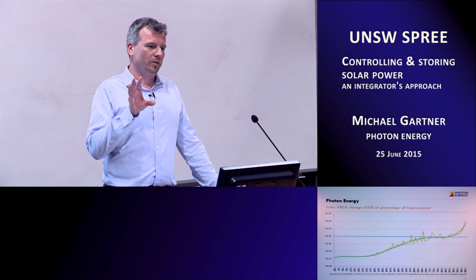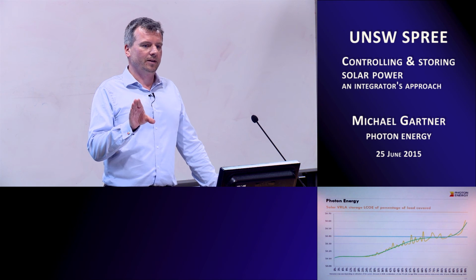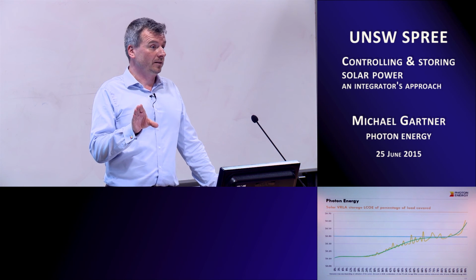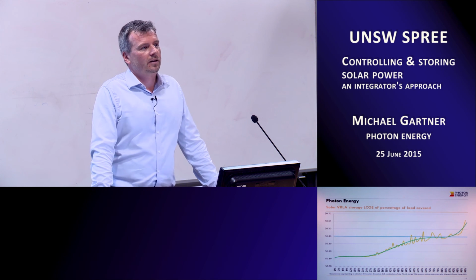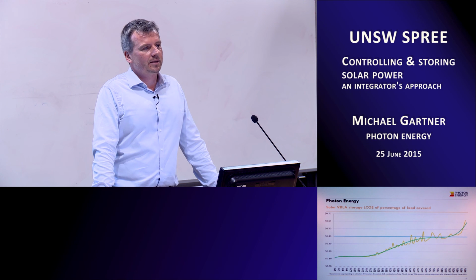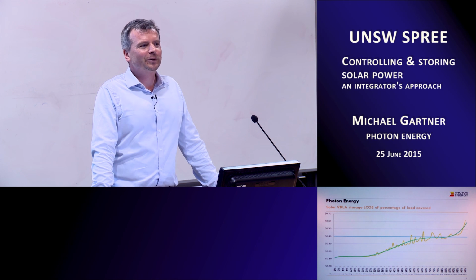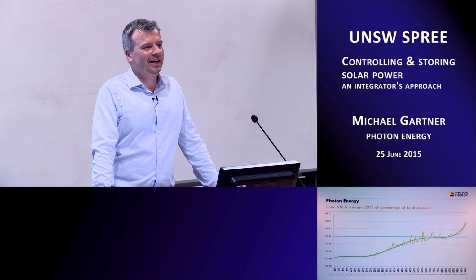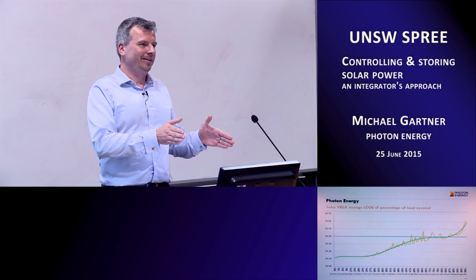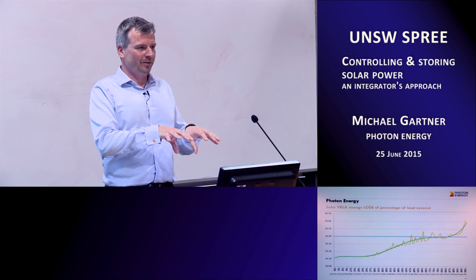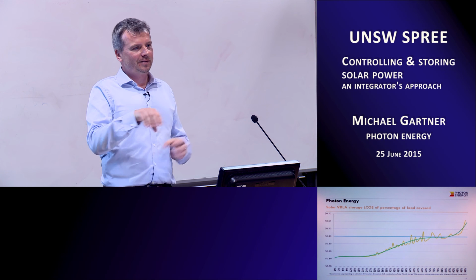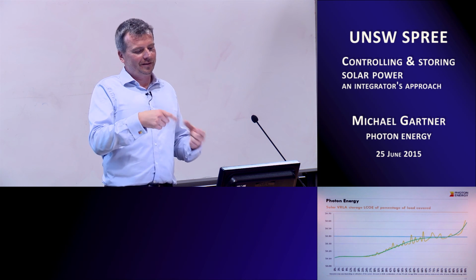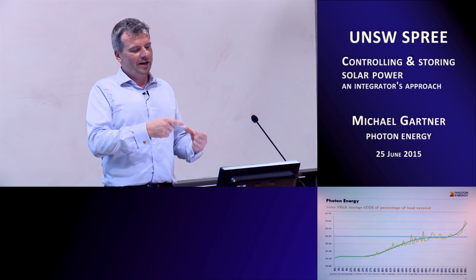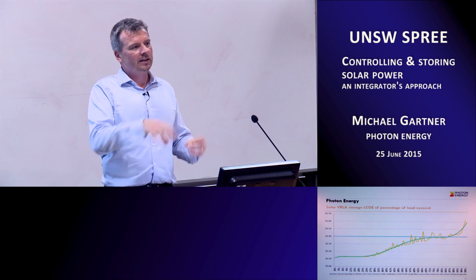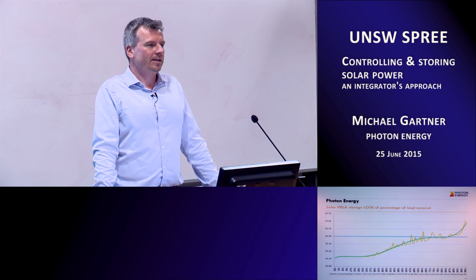We've noticed with lithium-ion technology that very often the bypass technology is already starting to be built in. So that's one aspect where it is. With lead acid, it's quite difficult, quite a challenge, because you don't have a BMS on each battery. But then again, within a lithium-ion system, you're generally talking about a cluster of cells controlled by one BMS, so the BMS won't necessarily react to one cell failure within one battery, but certainly between batteries, yes.